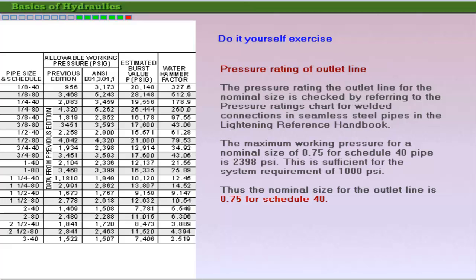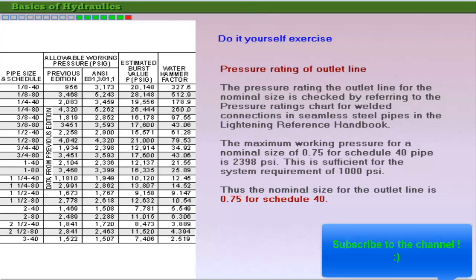Refer to the pressure ratings chart for welded connections in seamless steel pipes in the Lightning Reference Handbook to determine the pressure rating of the pump outlet line. The pressure rating of 2,398 PSI of the pipe is more than the maximum pressure of 1,000 PSI in the system. Hence, a pipe size of three-quarters of an inch for schedule 40 is suitable for the pump outlet.